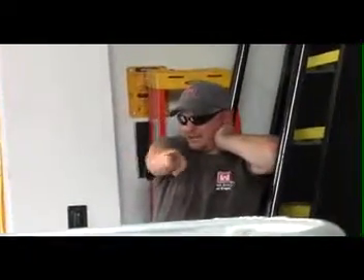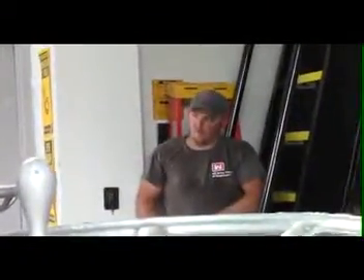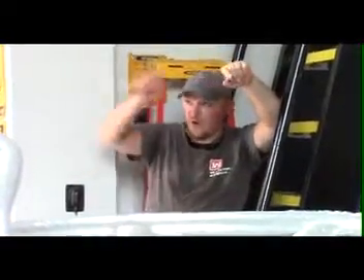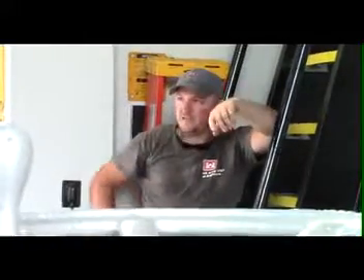So you've got to do something to keep that water from coming out, whether you have to work on the gate or whatever. Well, we've got a maintenance bulkhead outside. That row of 3 are what we call the emergency gates, and these 3 are the service gates. So when you say bulkhead, there's like a coffer dam? It's a lightweight version of the gates. We set it down with a 1-ton hoist, and then we can open both sets of gates in the series to get under them to inspect them. We just did yesterday. So when you say set it down, on cable and a track? Yeah, there's a 1-ton electric chain hoist and a trolley on the face of the intake structure. Set it straight down until it hits the bottom, come in, open these 2 gates, drain it, and then you go down and do what you've got to do.